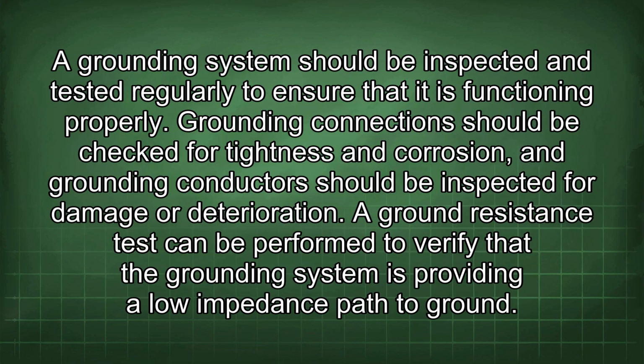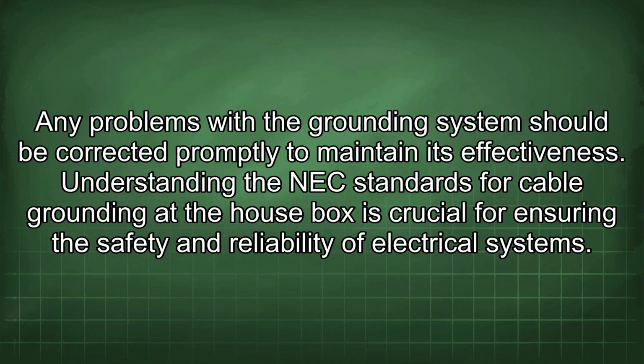A grounding system should be inspected and tested regularly to ensure that it is functioning properly. Grounding connections should be checked for tightness and corrosion, and grounding conductors should be inspected for damage or deterioration. A ground resistance test can be performed to verify that the grounding system is providing a low impedance path to ground. Any problems with the grounding system should be corrected promptly to maintain its effectiveness.